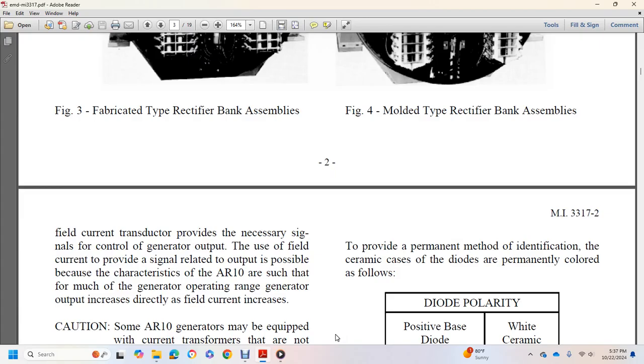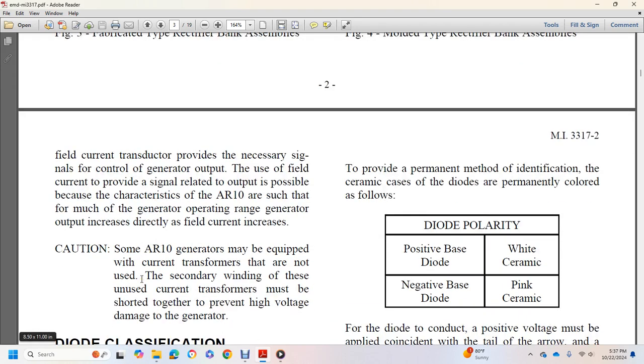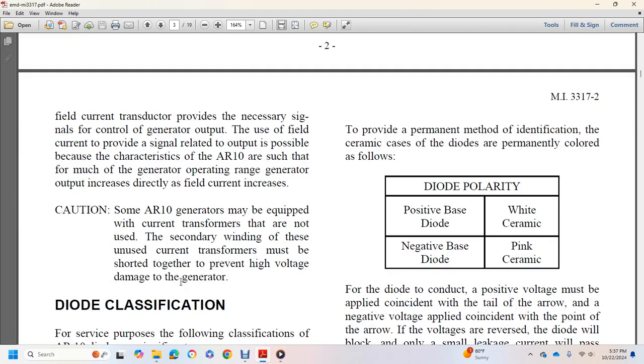The field current transducer provides the necessary signal for control of the generator output. The field current provides a signal related to output. Within the operating range, generator output increases directly as the field current increases. Some of the AR10 generators are equipped with current transformers, but the secondary windings are unused. The unused current transformers must be shorted together to prevent high voltage damage to the generator.